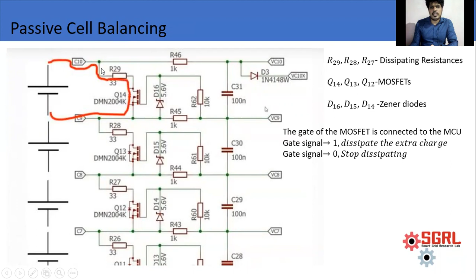We can calculate the dissipated power through this resistance: it equals I squared R, the square of the balance current multiplied by the balance resistance. The power rating of the resistance should be higher than this dissipated power. The voltage rating of the MOSFET should be 2 or 3 times the cell maximum voltage, and the current rating of the MOSFET should be 2 or 3 times the balance current. Likewise we can select the MOSFET voltage and current ratings and the resistance power rating.